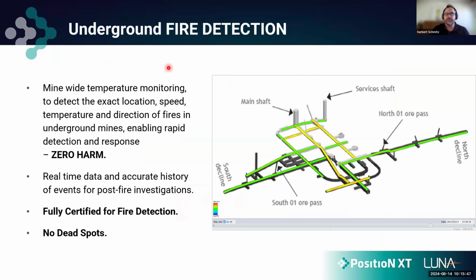And so we've alluded to this before, that one of the main applications within mining in tunnel environments would be fire detection, where we would run this fiber through the existing infrastructure. What this allows us is to detect the exact location of the fire, the speed and direction of the movement of the fire, as well as the hot gases. That ultimately enables a better response for the first responders and the rescue team, knowing exactly what the temperature is, in which direction it's moving, what's the cold air side. We know where the temperature is along the entire fiber optic cable, so we have a lot more information to deal with.